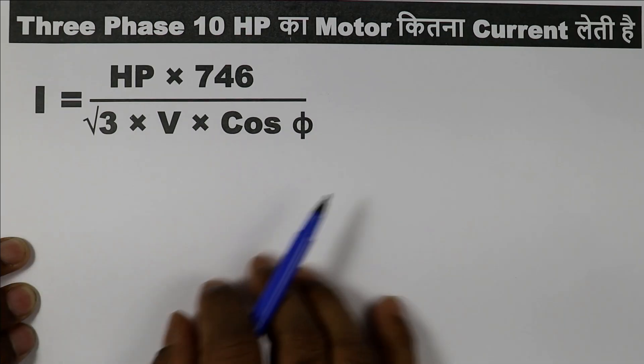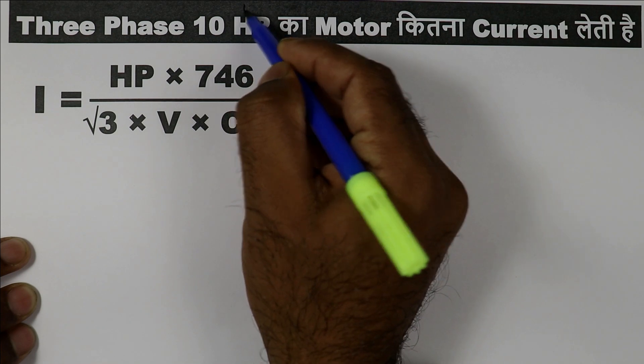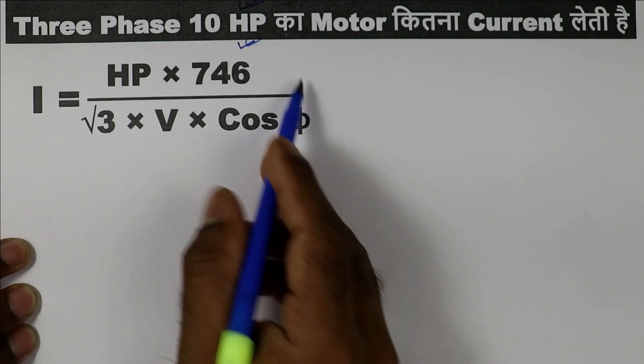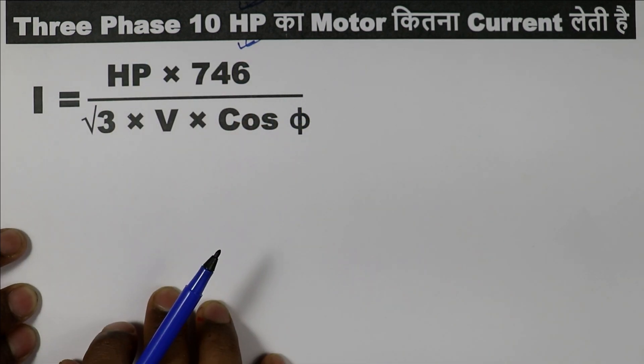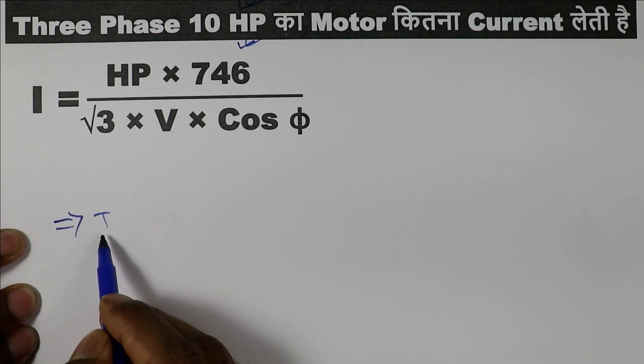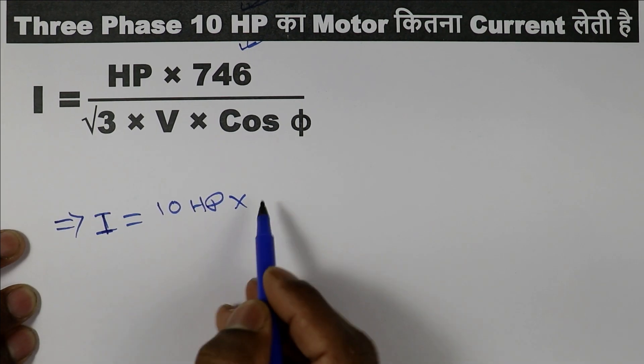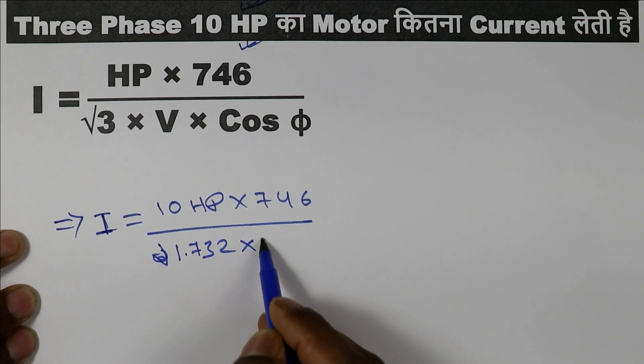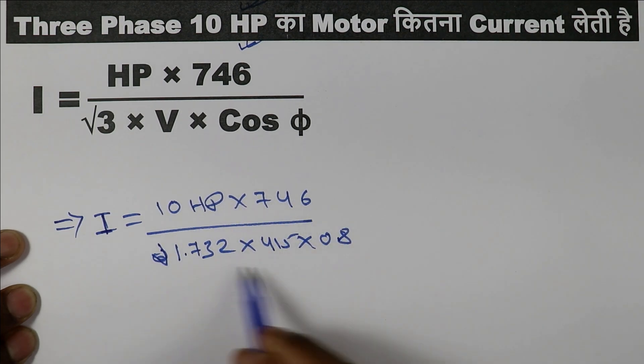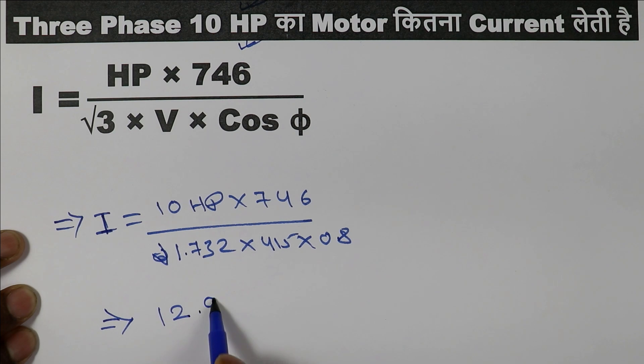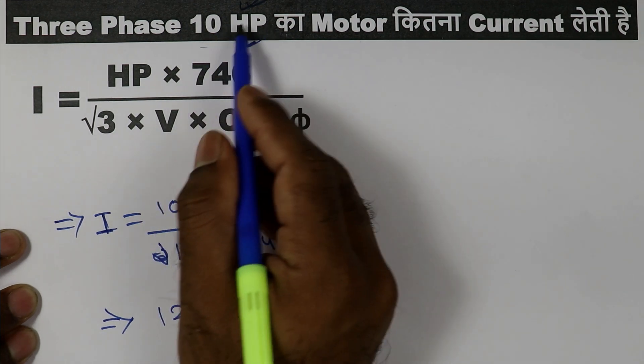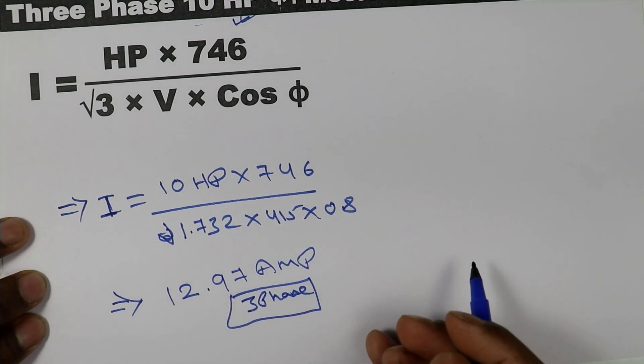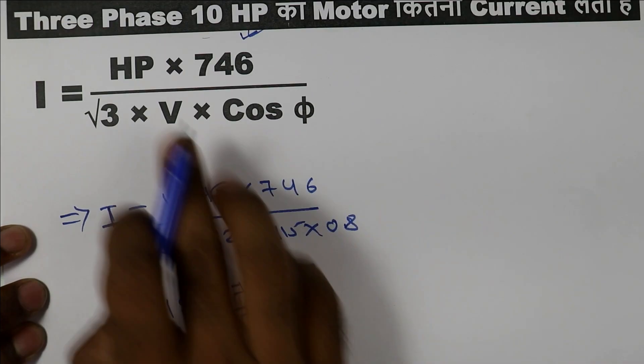Now let us move on to the horsepower question. The question is the same but in place of kilowatt, horsepower is given. For a 10 horsepower 3-phase motor, the formula becomes: 10 HP into 746, divided by root 3 (1.732), multiplied by voltage (415V), multiplied by power factor (0.8). When you solve this, the answer comes as 12.97 ampere — that is the current rating of a 10 HP 3-phase motor. We are not talking about single phase for now.